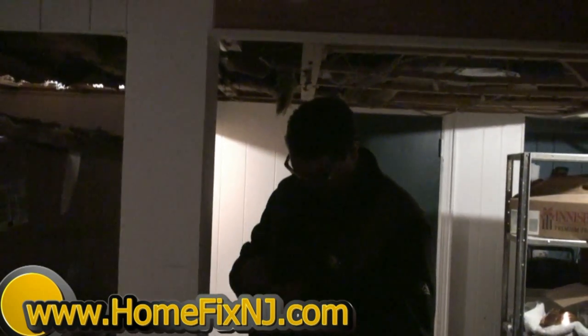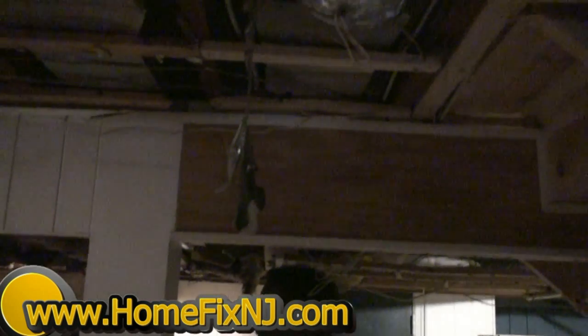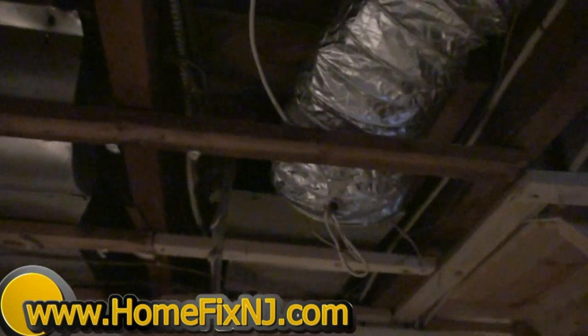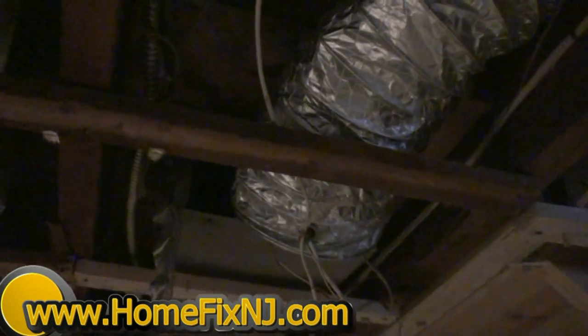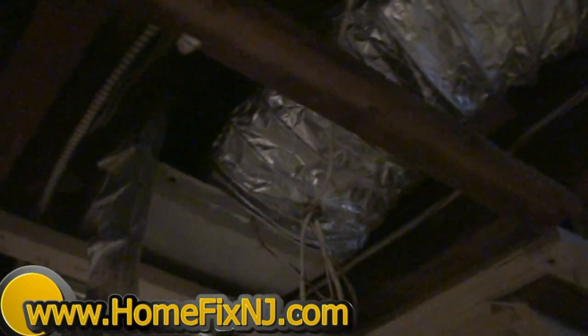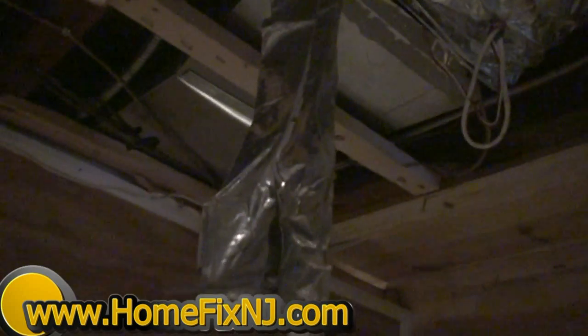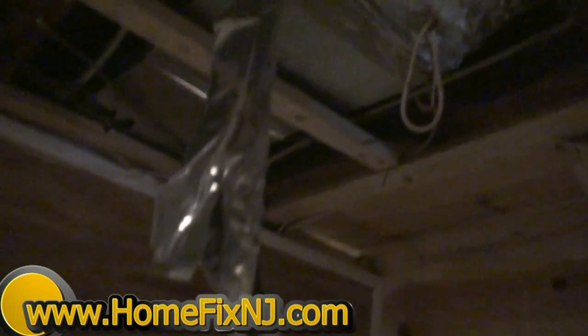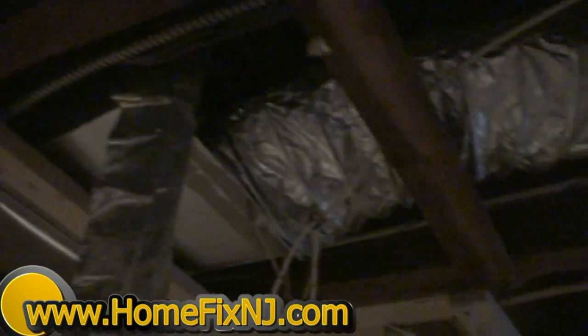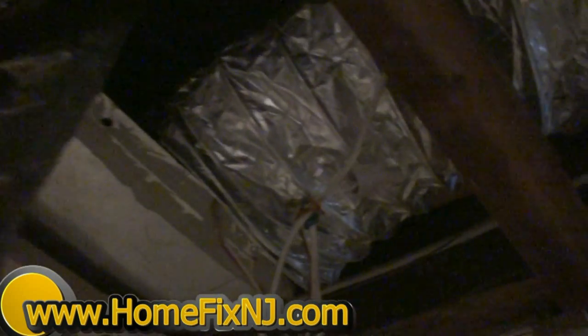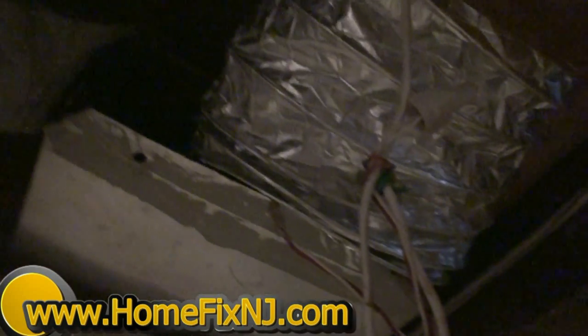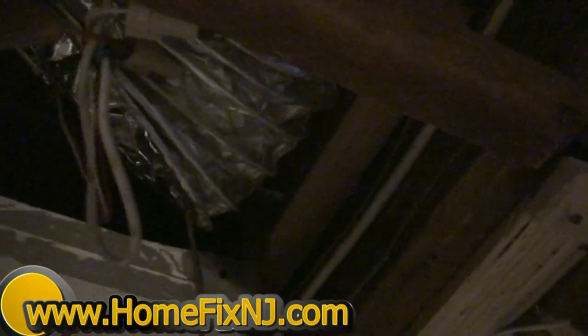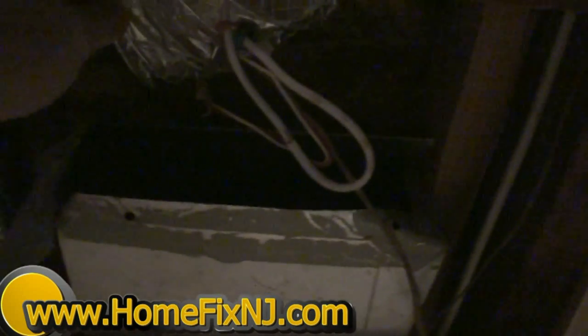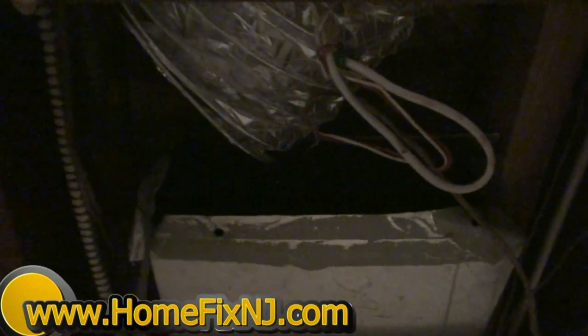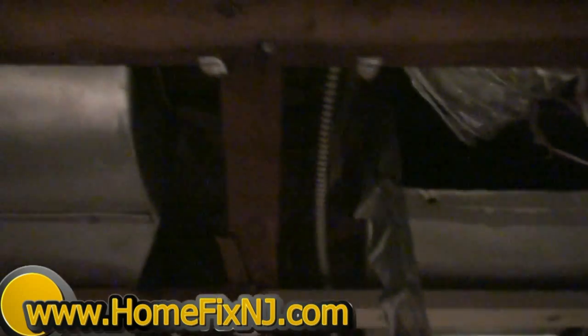So what we found in the basement was some substandard contracting work that had been done previously during a kitchen renovation. Some flexible duct work had just been duct taped to some rigid ducts that had been truncated during laying of a new floor. Duct tape, although it's called duct tape, you don't want to use duct tape on ducts. What you want to use is UL 181 foil tape and mastic, and we're going to show you that in a second.